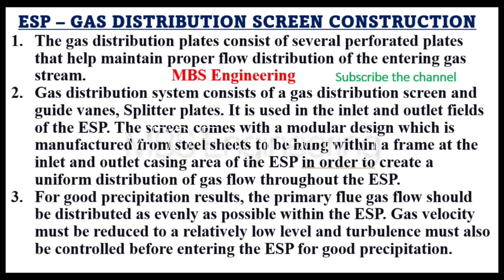The screen comes with a modular design, which is manufactured from steel sheets to be hung within a frame at the inlet and outlet casing area of the ESP, in order to create a uniform distribution of gas flow throughout the ESP. Point 3: For good precipitation results, the primary flue gas flow should be distributed as evenly as possible within the ESP. Gas velocity must be reduced to a relatively low level and turbulence must also be controlled before entering the ESP for good precipitation.